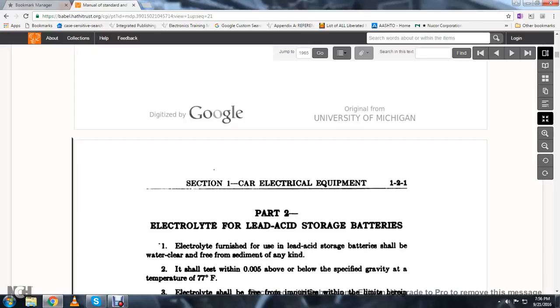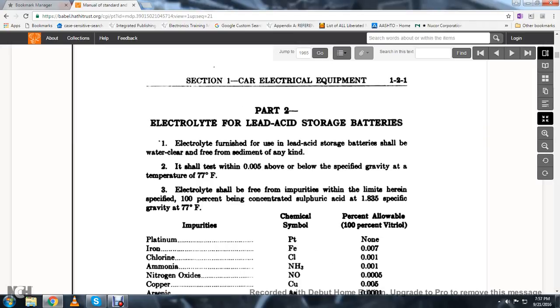Section one, Car Electrical Equipment. American Association of American Railroads Electrical Division, Part Two. Electrolyte for lead acid storage batteries: electrolyte furnished for the use of lead acid storage batteries shall be water, clear, free of sediment of any kind, and shall test at 0.005 above or below the specified gravity at a temperature of 77 degrees Fahrenheit. Electrolyte shall be free of impurities within the limits herein specified.